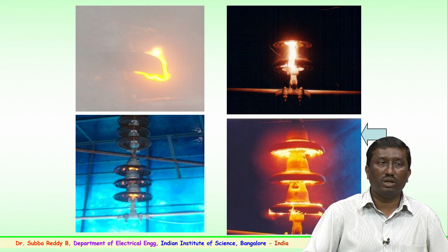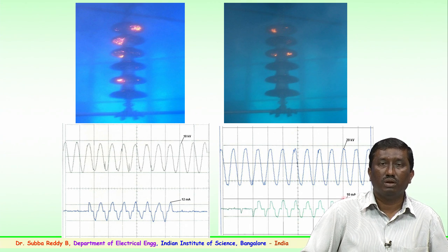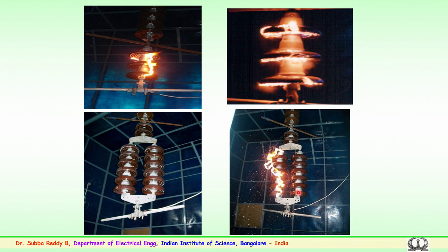This is similar to the field, where the same phenomena could happen. So, a lot of experiments have been carried out for the normal string and the string containing the field reduction electrodes which have been developed in the laboratory. We have tried to see various configurations for a double tension arrangement, a single type of insulators.